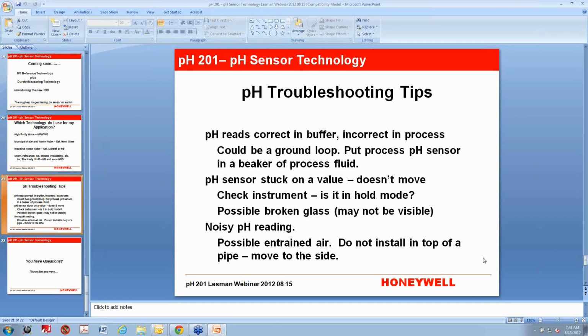Another issue I see is the pH sensor gets stuck on a value and doesn't move. And we all know that in a live process, your pH is not going to be 7.8 all the time. It's going to move a little bit. So if it's not moving, the first thing I would do, of course, is make sure that somebody hasn't put the instrument in hold, because it may be holding that value because somebody's done something with it. But more than likely, it could be broken glass. What happens is when the glass breaks, you get a dead short between the measuring electrode and the reference electrode. And so then it just sticks on a number.